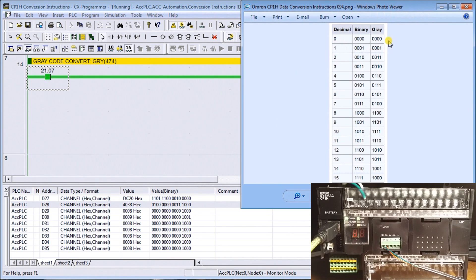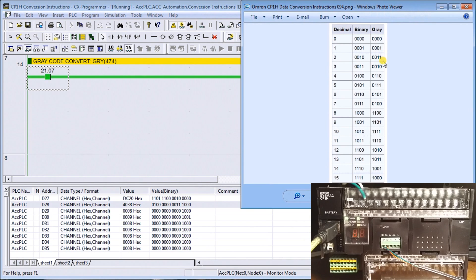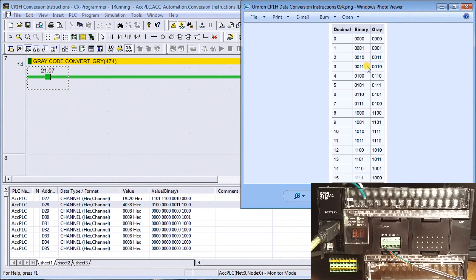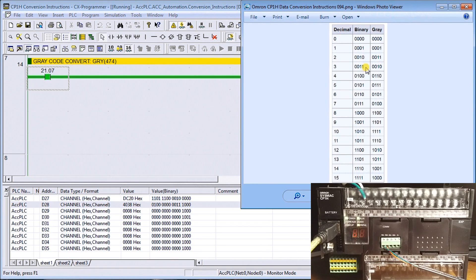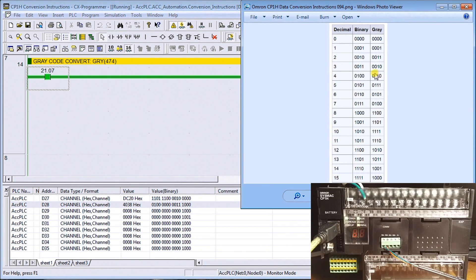You can see here, I have a small chart. It gives me a four bit. You'll see that gray code is only one bit changes as it goes, say from one to two and from two to three. Whereas some of these other ones, there's several bits that change. If we look at three to four, we have three bits change here, whereas in gray code we only have one bit change. That's the advantage of using the gray code within the controller.